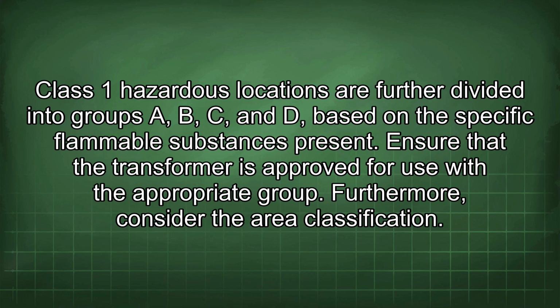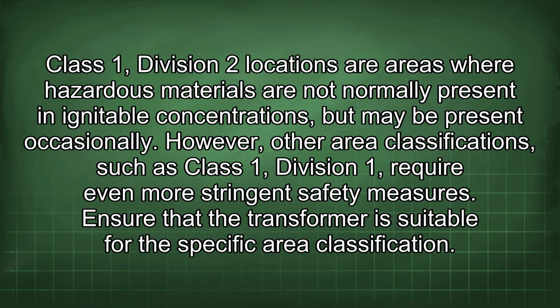Furthermore, consider the area classification. Class 1, Division 2 locations are areas where hazardous materials are not normally present in ignitable concentrations but may be present occasionally. However, other area classifications, such as Class 1, Division 1, require even more stringent safety measures. Ensure that the transformer is suitable for the specific area classification.